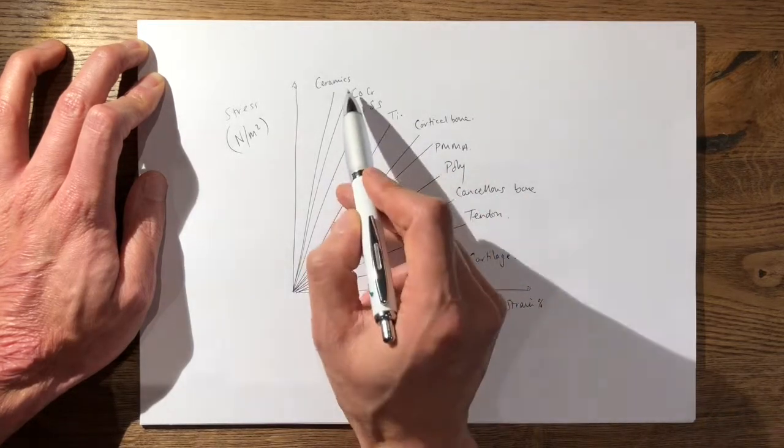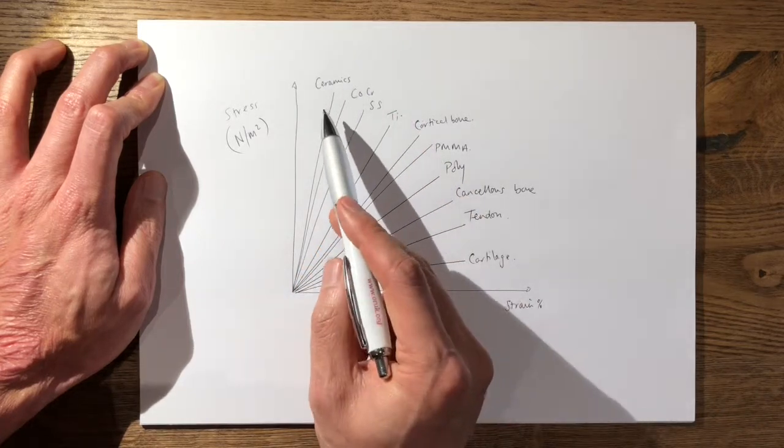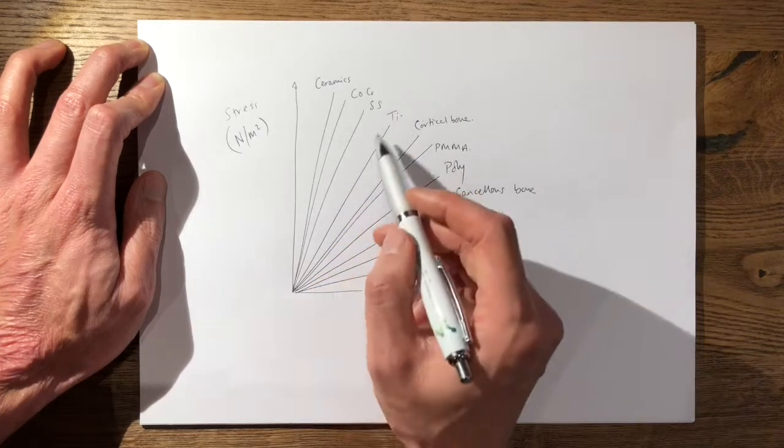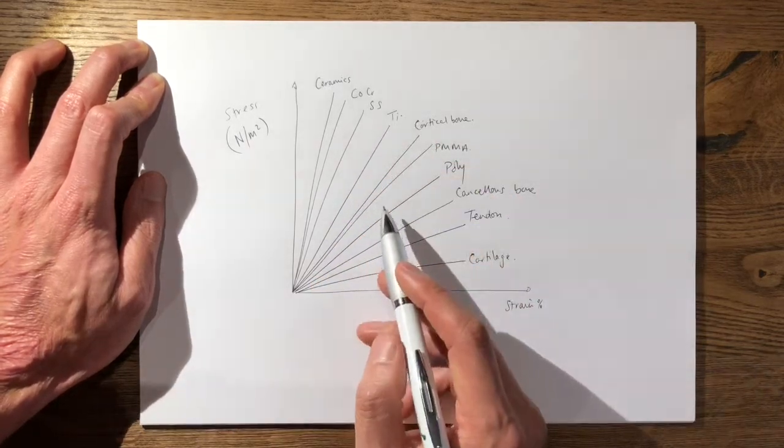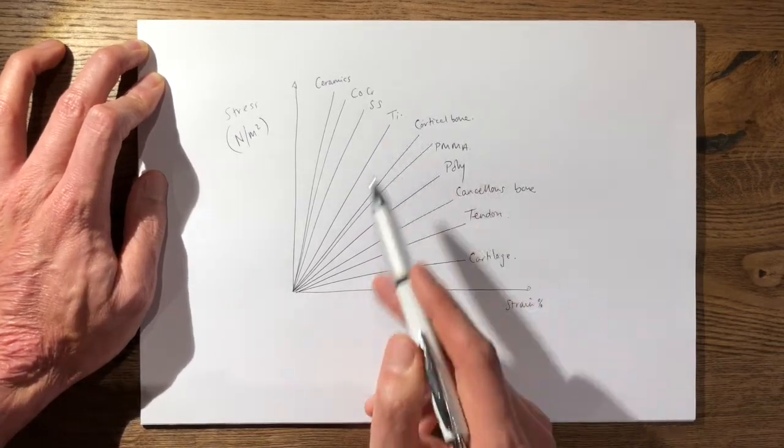This is also the reason why you don't see cobalt chrome used in hip stems and you're more likely to see a material such as titanium because it has a more similar Young's modulus to cortical bone.